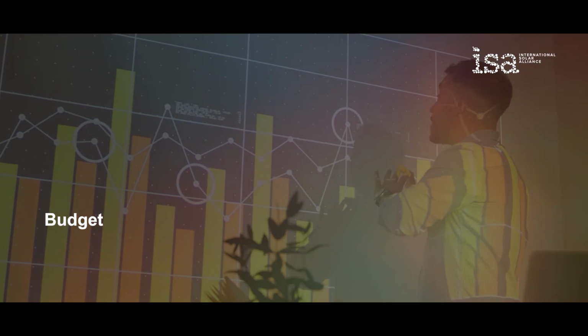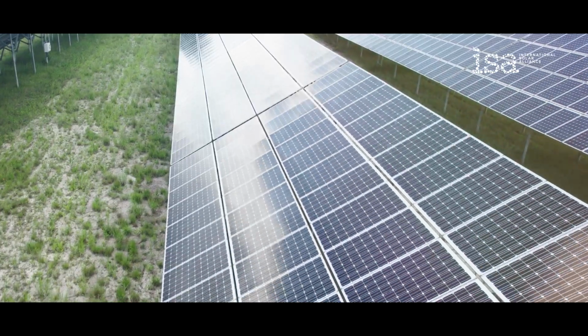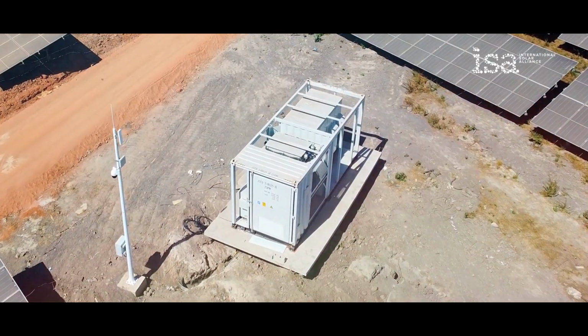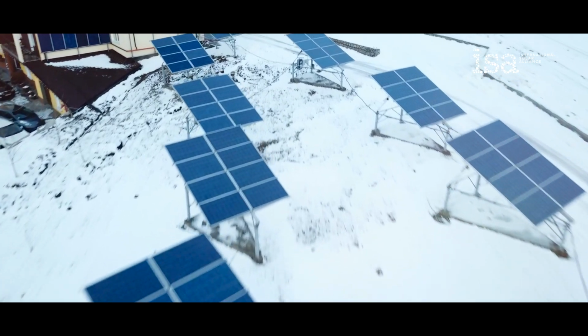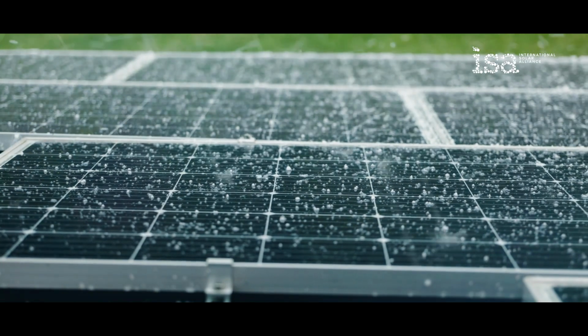In a nutshell, a very fine balance is to be made between the energy requirement during non-sun hours, PV capacity of the plant, charging rate of the batteries to meet up the demand, system voltage, climatic and environmental conditions of the location, and depth of discharge for determining the battery capacity.